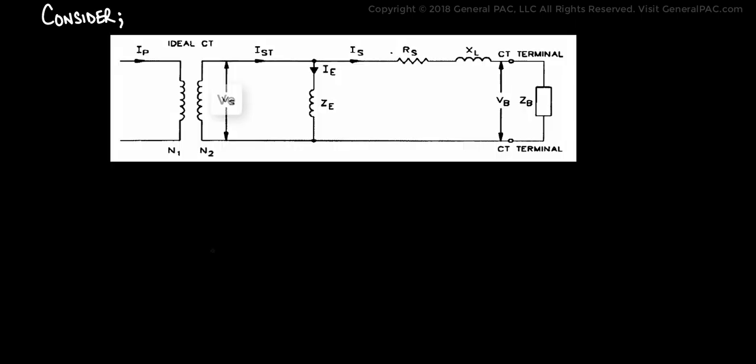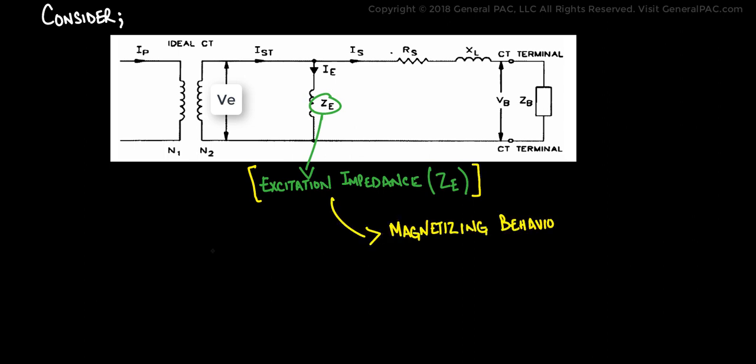This equivalent circuit model of a CT is drawn as you can see on the screen. There is an excitation impedance which we will represent by ZE. It tells us about the magnetization behavior of the CT core. And this ZE branch or the ZE value, or the excitation branch, it is non-linear in nature.